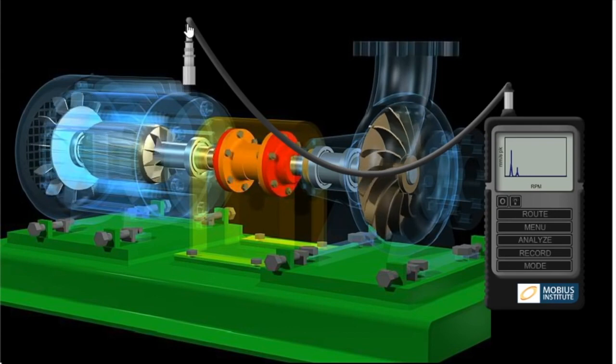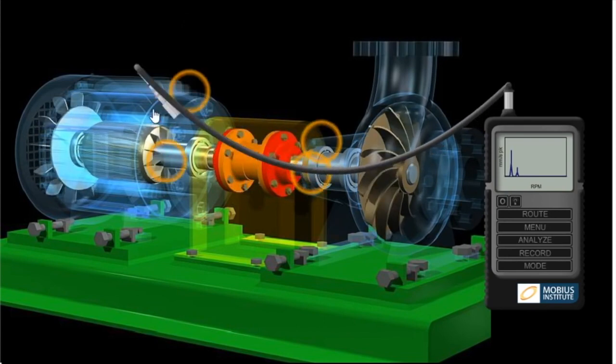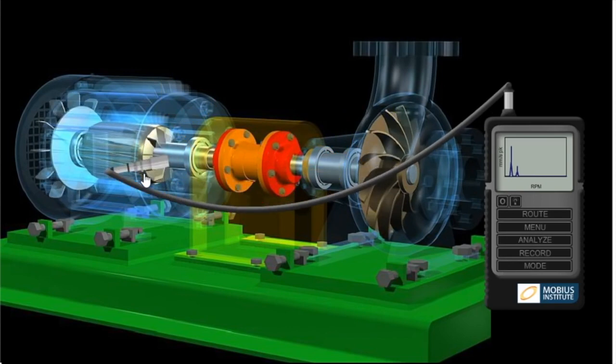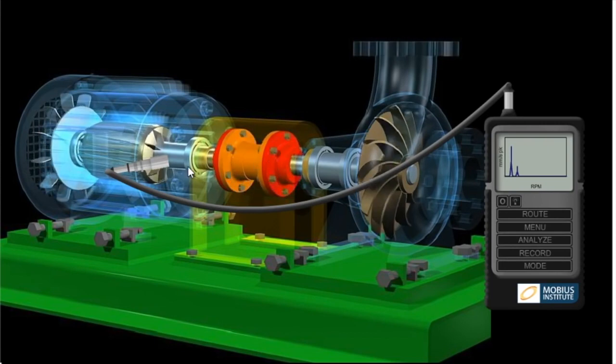But the fact is, when we mount it up on top, that is sensitive to the vertical motion. Whereas if I move it to the horizontal location, that is now much more sensitive to the horizontal motion. So for example, if it was rocking back and forward due to looseness or resonance, then the horizontal measurement will tell us about that.